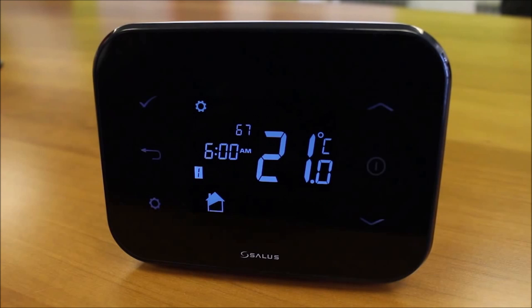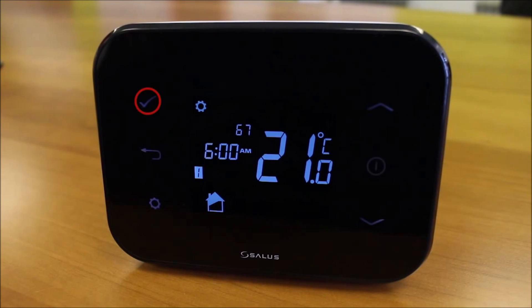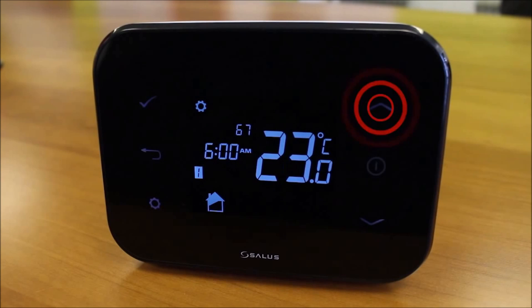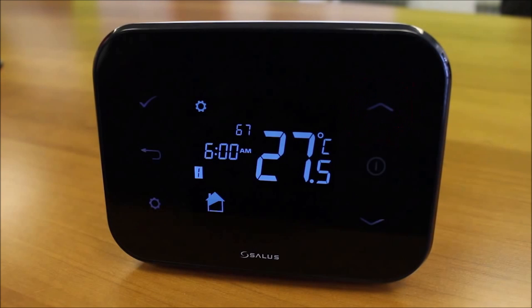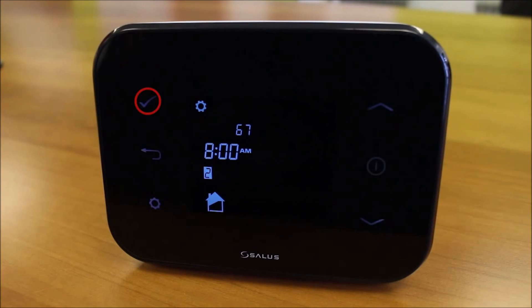When you see 6 and 7 showing, this will represent your weekend times. Program 1: use the UP or DOWN arrow key to change the first time you want the heating on in the morning. Press the Tick to confirm, and the minutes will flash. Use the UP and DOWN arrow key to change the minutes and press the Tick to confirm. The temperature will now flash; use the UP or DOWN arrow key to change the temperature to what you require. Press the Tick to confirm and repeat the process for the remaining programs.